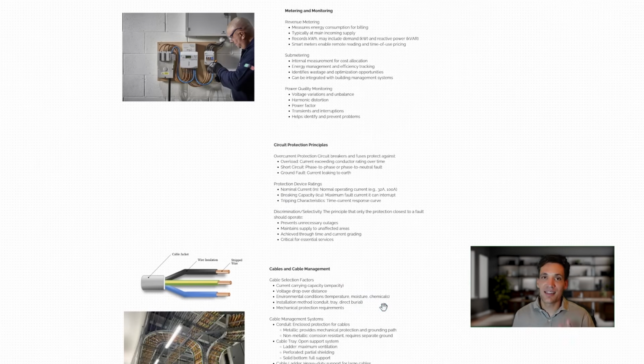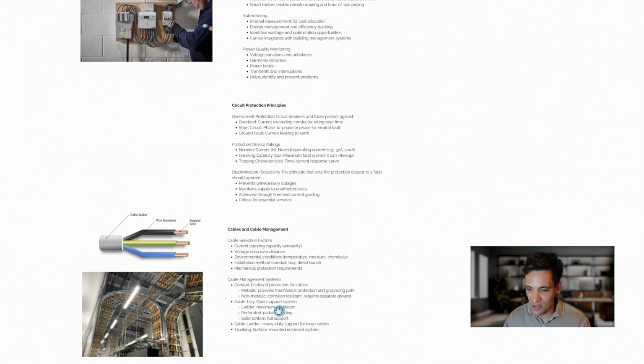So it's really important to understand broadly how all these work and the specific design constraints and characteristics that impact them. So with cables, it's the current carrying capacity is critical, and the distance the cable has to run, which will impact the voltage drop, which impacts the size of the cable, as well as any environmental conditions like UV, like potential damage from other objects, and mechanical protection requirements.